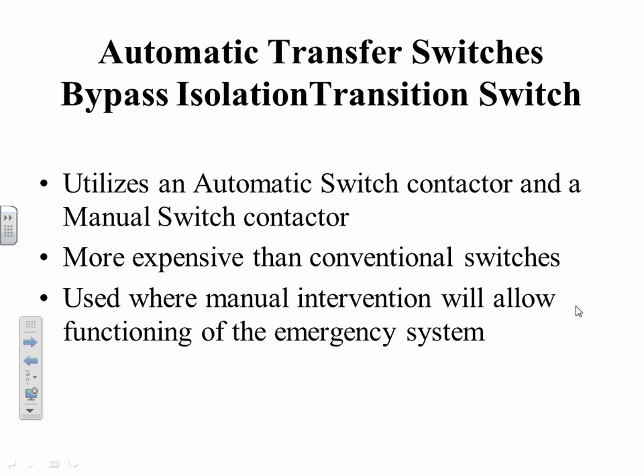So bypass isolation has a different requirement and a different reason. It uses an automatic transfer switch contactor and a manual switch contactor, both connected to the same load. I'll tell you right now that anytime you double the amount of contactors in a transfer switch, the price is going to go up. Very true. You've also spent more money to wire it that way and on the wire itself. So it's going to be more expensive than conventional switches.